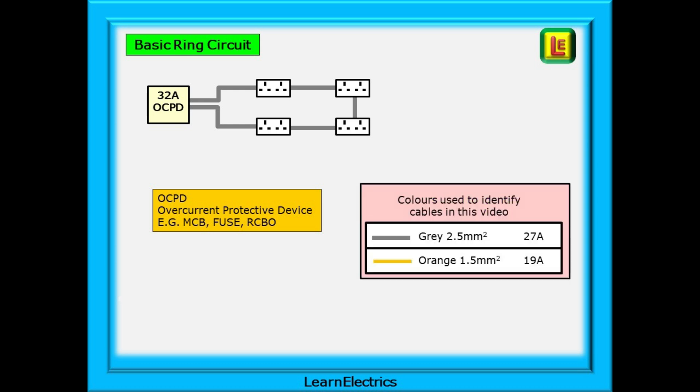To begin with, we'll assume just a basic ring circuit in a basic domestic dwelling under normal conditions. In order to help with understanding the drawings, we'll colour the different sized cables as follows: 2.5 twin and earth will be coloured grey on the drawings and orange will be used to show 1.5 twin and earth cable. Notice also the maximum current carrying capacity of each sized cable under normal conditions.